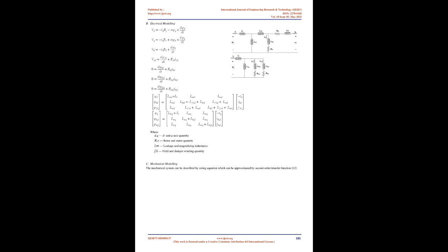At time t equals 25 seconds, the utility main circuit breaker was opened to study the microgrid response during islanding mode. The frequency and voltage were disturbed due to the sudden and significant loss of the utility, and both controllers, the diesel generator governor and the excitation system, responded immediately. During the frequency transient response, the generated power in the microgrid was higher than the load demand, thus the diesel engine speed increased up to 60.07 Hz, then it decreased to 59.98 Hz before it recovered back to 60 Hz within 4 seconds. Although the frequency recovery was much slower than the voltage, the system voltage showed a high spike of approximately 1.5 kV, which has to be considered in the protection design, for example by including surge arresters.